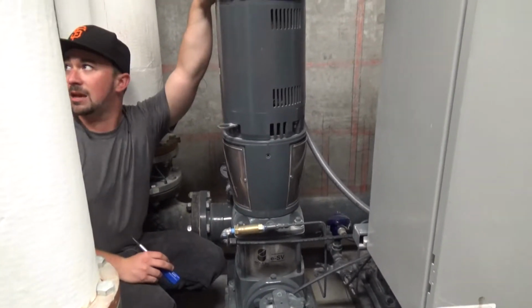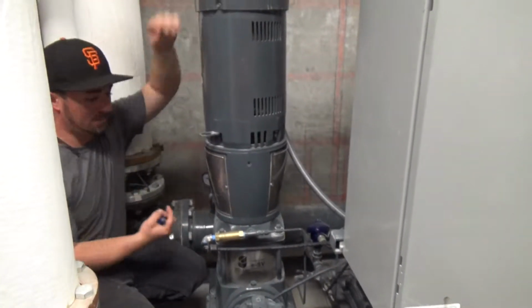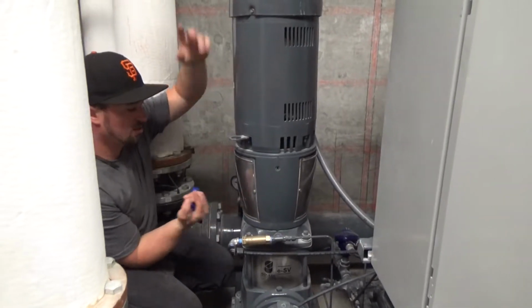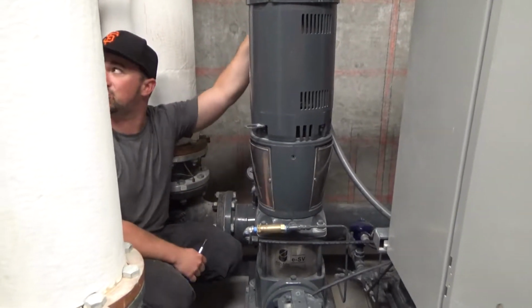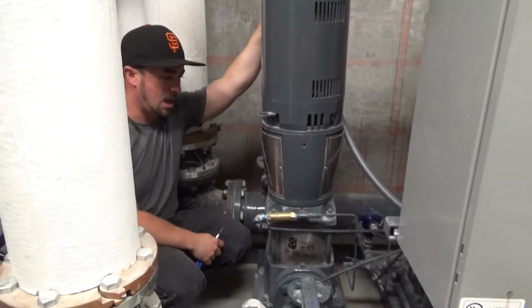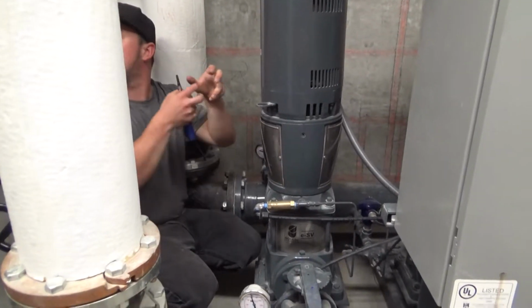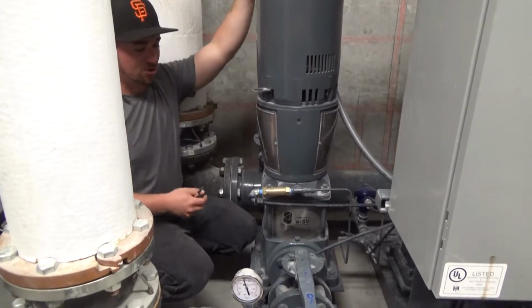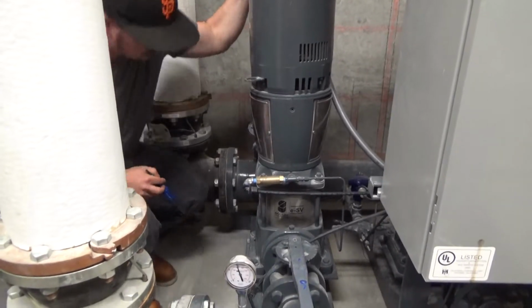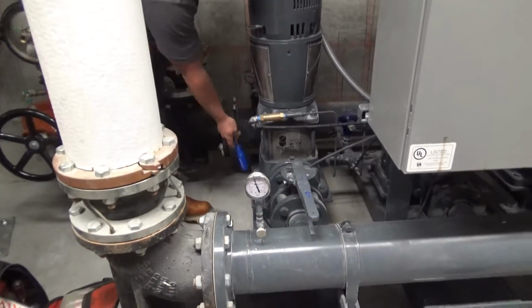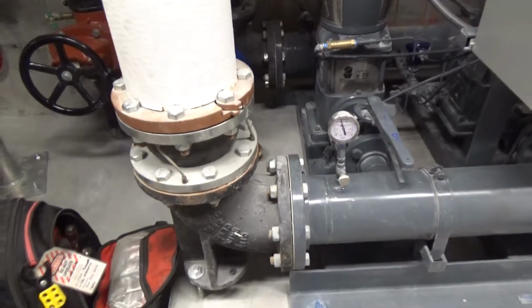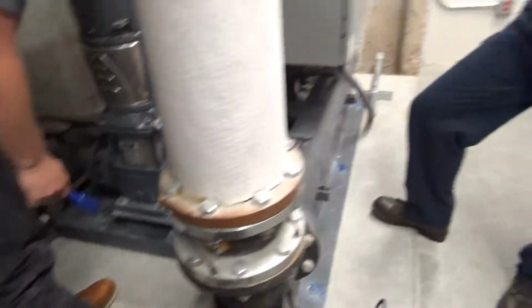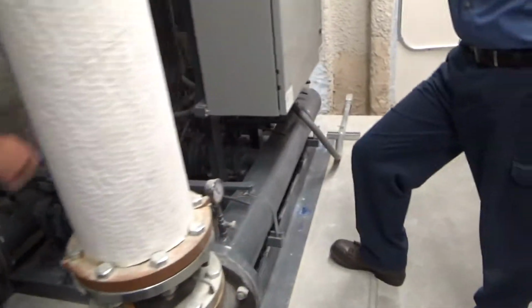There's no need for alignment on the 2 shafts. They're held together in the center, and there's no need to sit there with a straight edge and try to align them up, which is very nice. The coupling is just 2 little cast iron pieces that go together with 4 bolts. So that's the pump. You do have a drain right here if you guys ever need to drain it off. And you have 2 isolation valves on the in and the out on both sides of the pump for service.